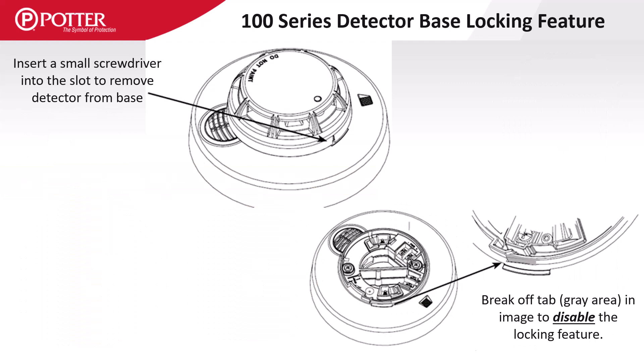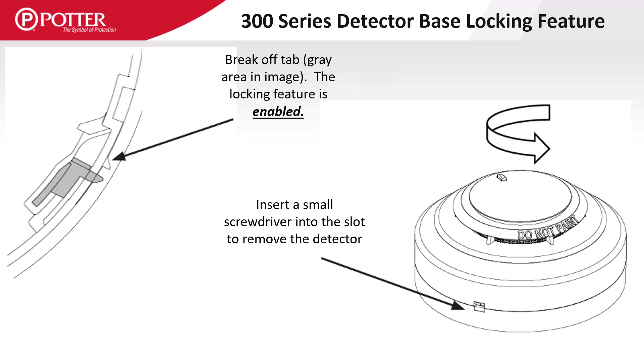On the 100 series bases, there is a tab that needs to be broken off when disabling the locking feature of the detector head. On the 300 series, the locking feature works exactly the opposite — to enable the locking feature, break the tab as shown in the illustration.